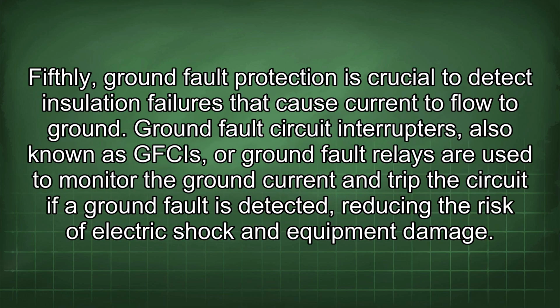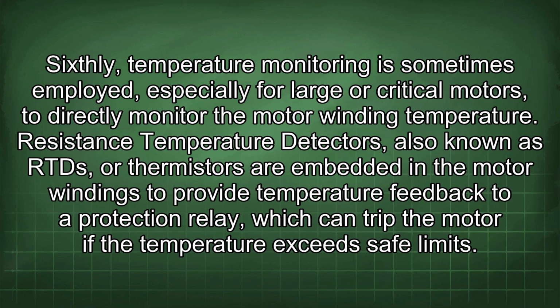Fifthly, ground fault protection is crucial to detect insulation failures that cause current to flow to ground. Ground fault circuit interrupters, also known as GFCIs, or ground fault relays, are used to monitor the ground current and trip the circuit if a ground fault is detected, reducing the risk of electric shock and equipment damage. Sixthly, temperature monitoring is sometimes employed, especially for large or critical motors, to directly monitor the motor winding temperature. Resistance temperature detectors, also known as RTDs, or thermistors, are embedded in the motor windings to provide temperature feedback to a protection relay, which can trip the motor if the temperature exceeds safe limits.